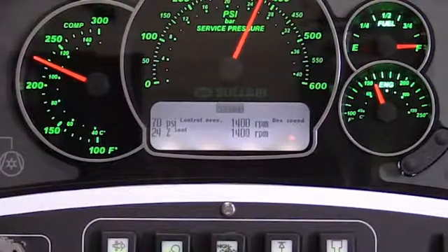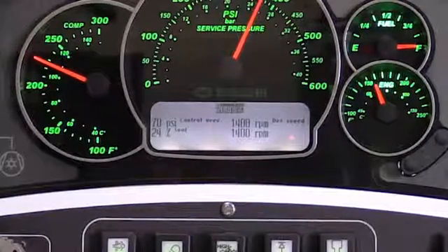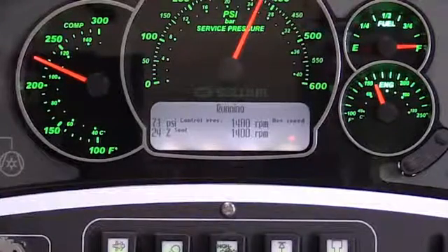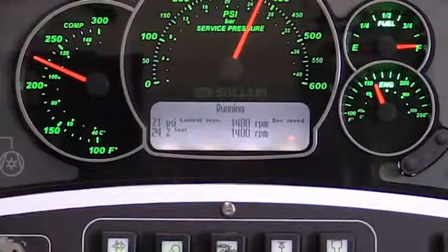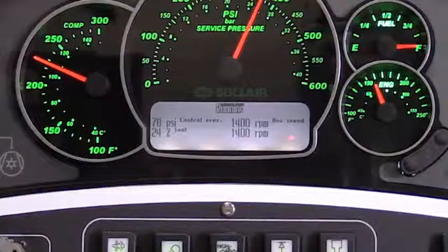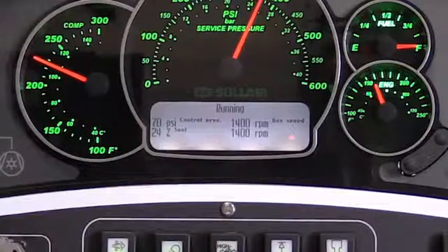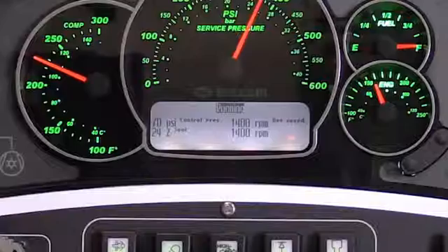P2 is located in the control circuit. With 70 pounds on the control circuit and on P2, the C-Pro panel can use this information to determine whatever the desired engine RPM should be. Again, this is on the control circuit, which is also closing the inlet valve or allowing it to open as the signal goes away. So the inlet and the throttle react as one.